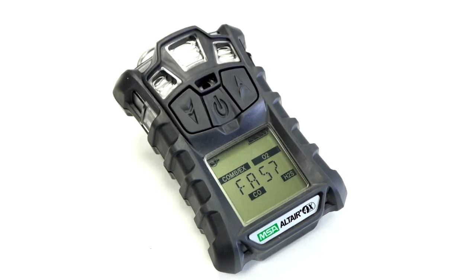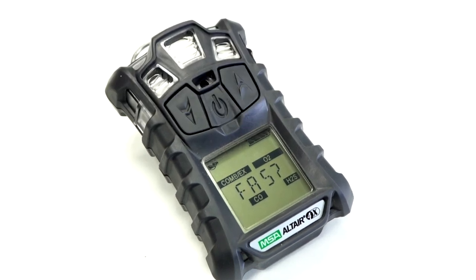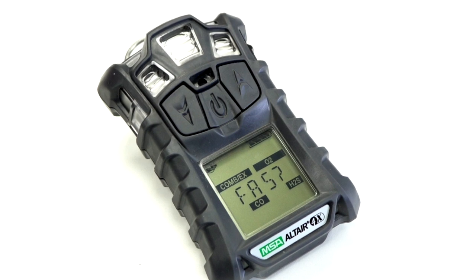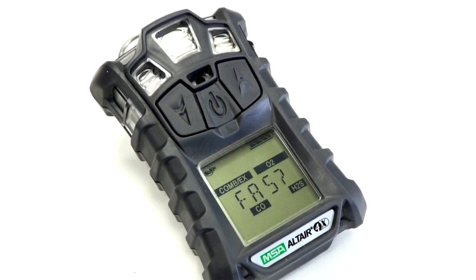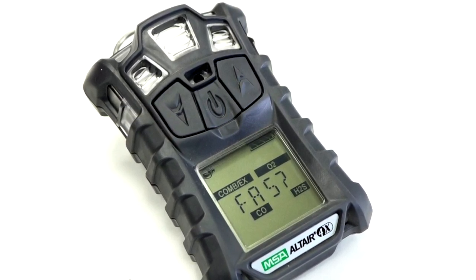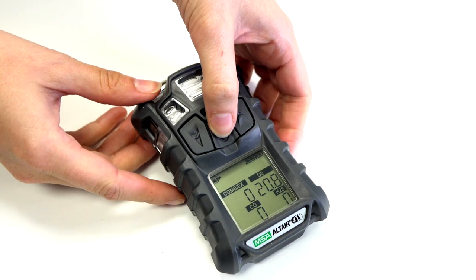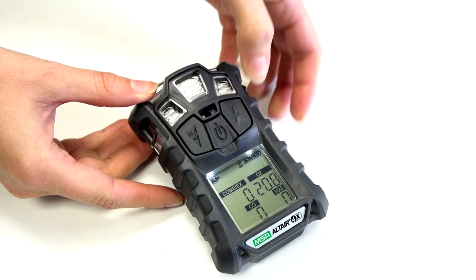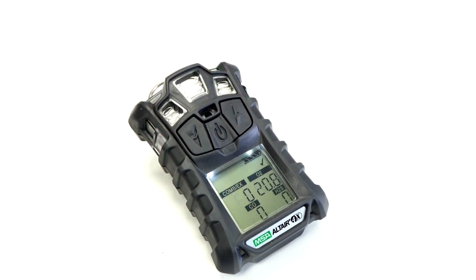If FAS should display on the screen, it means the unit wants to perform a fresh air calibration. This must only be carried out in an area which is completely free of hazardous gas. To confirm that you want to go ahead with the fresh air cal, press the power button. To cancel, press the right hand arrow. The unit is now in measurement mode.